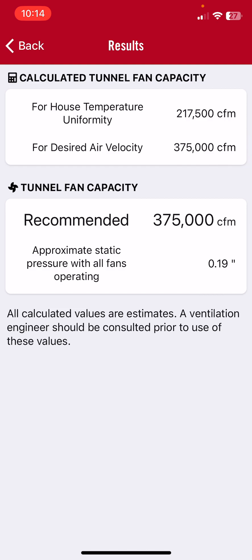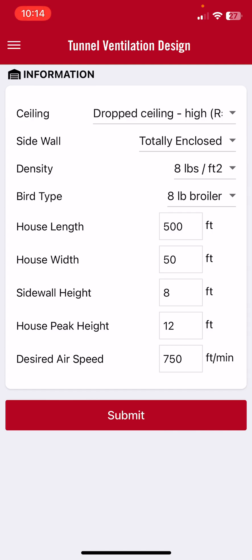Whichever of those two is the biggest is what we have to use. So the recommended tunnel fan capacity to promote proper house temperature uniformity — no more than a five degree temperature rise — and to produce an air speed of 750 feet per minute is 375,000 CFM. The calculator also provides an estimated operating static pressure of approximately 0.19.